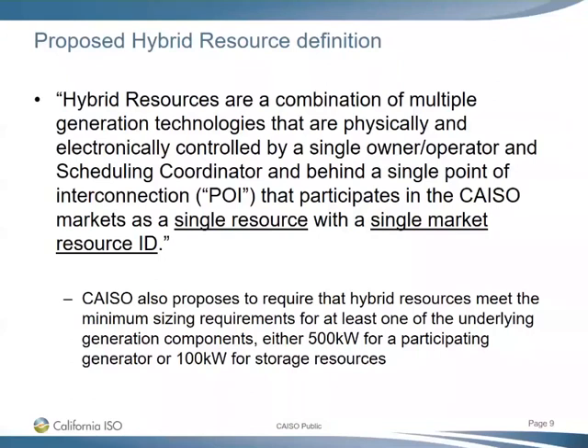John asked whether the definition of 'multiple generation technologies' includes configurations like a combined cycle plant with a steam turbine and combustion turbine. Chris confirmed that a combined cycle would not qualify as a hybrid resource under this definition — it would be considered a single participating generator needing to meet the 500 kW requirement. The intent is more about multiple different fuel sources, such as the traditional storage-and-solar concept, rather than multi-stage generators of the same fuel type.